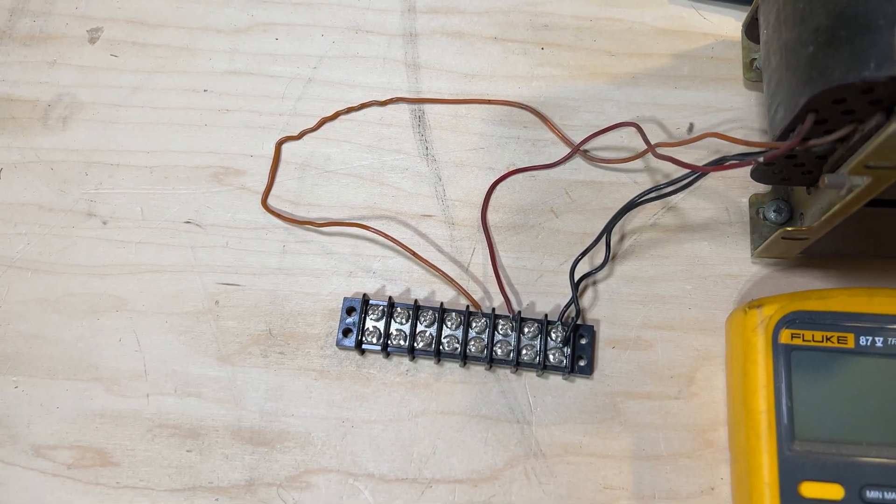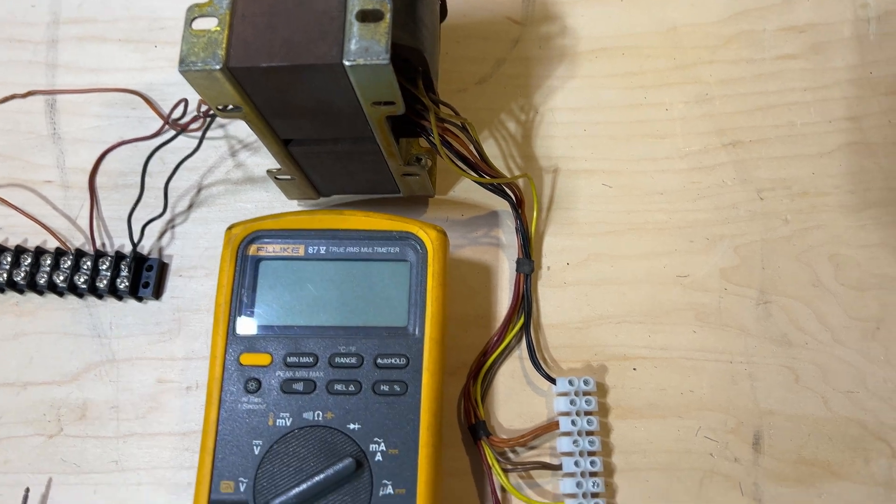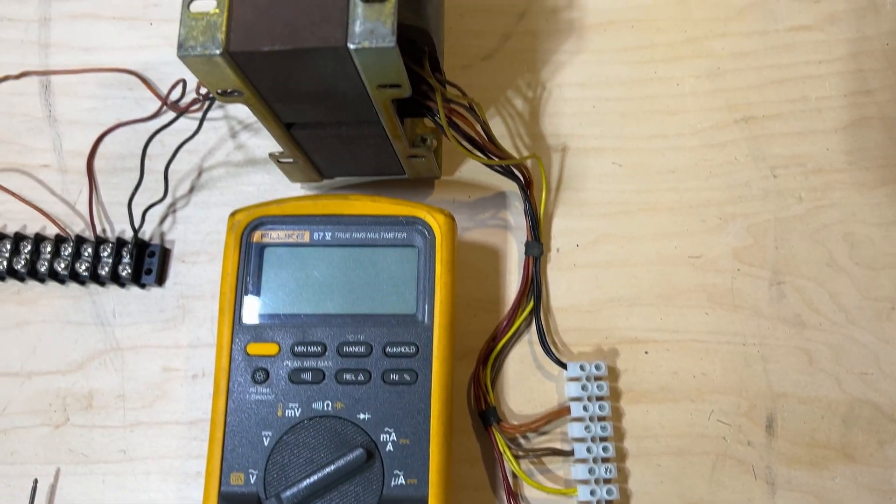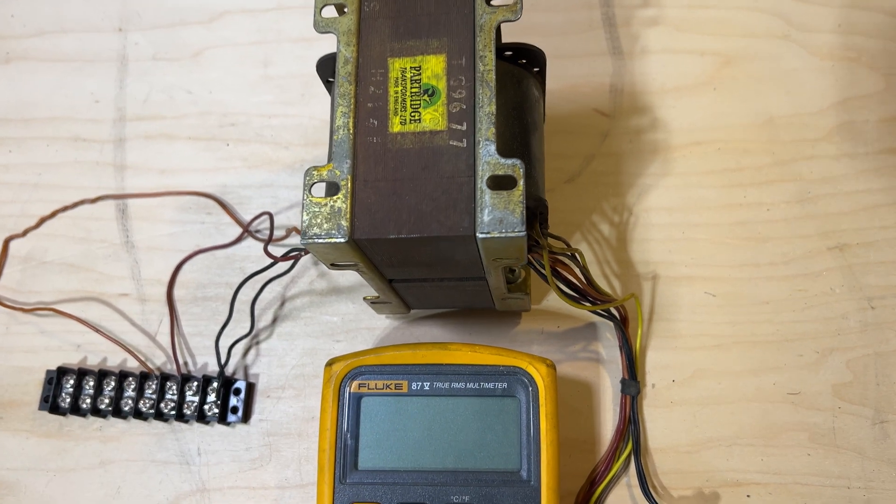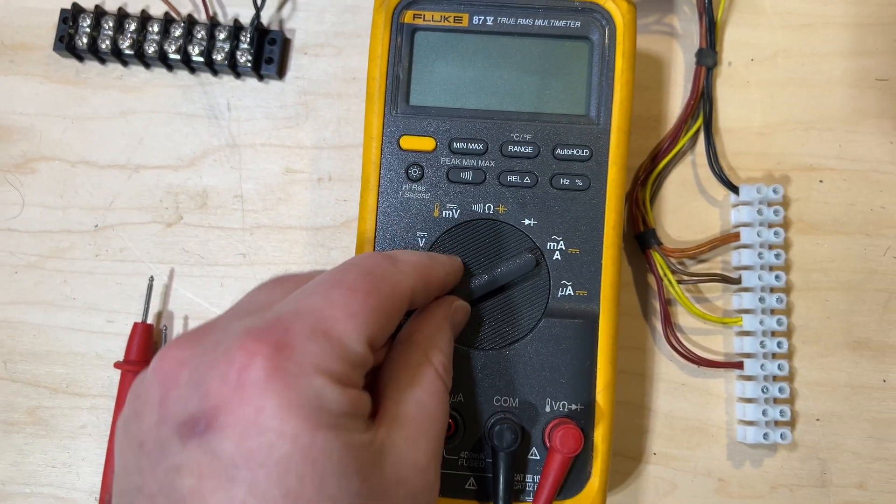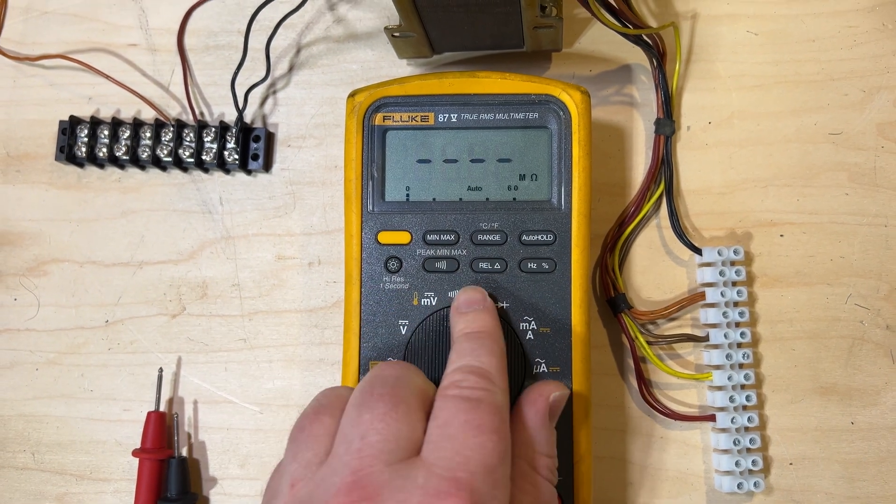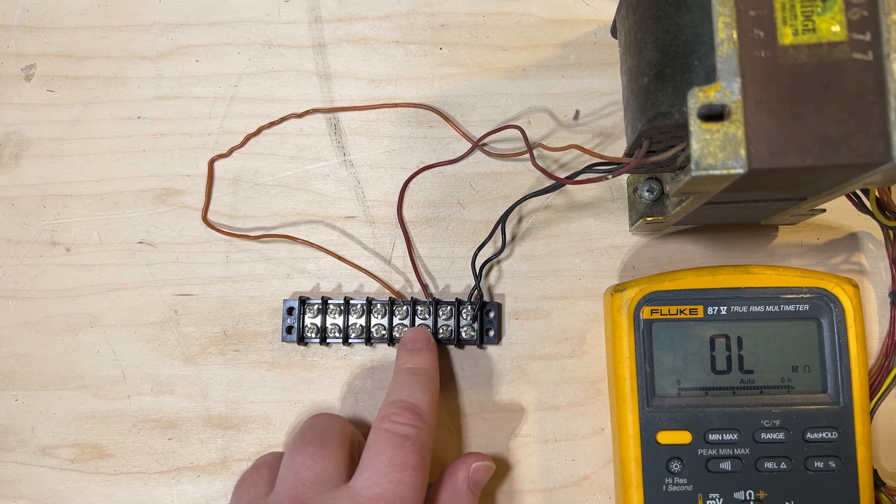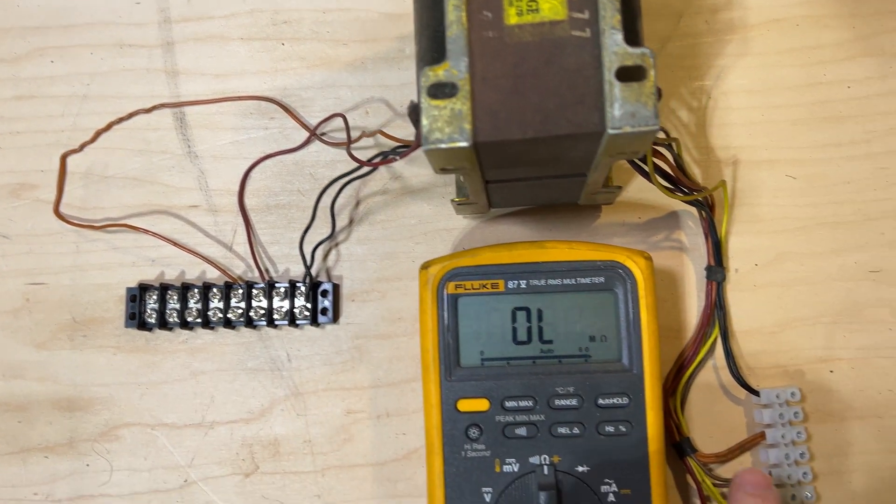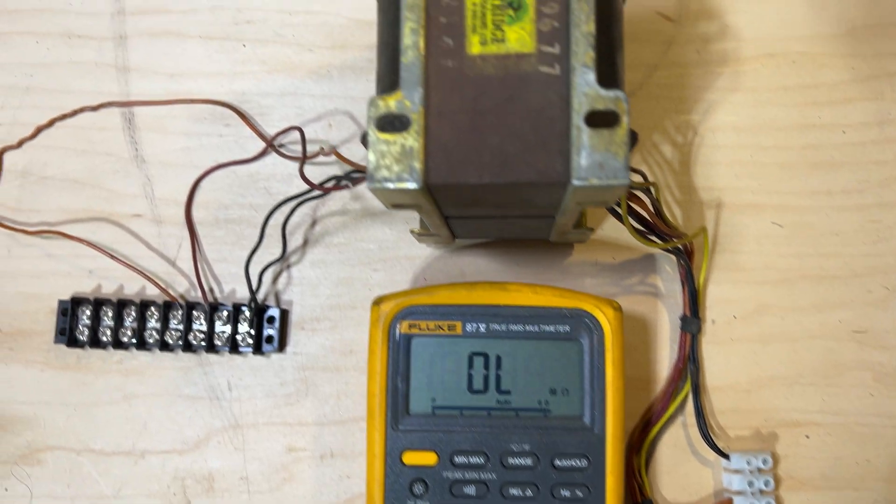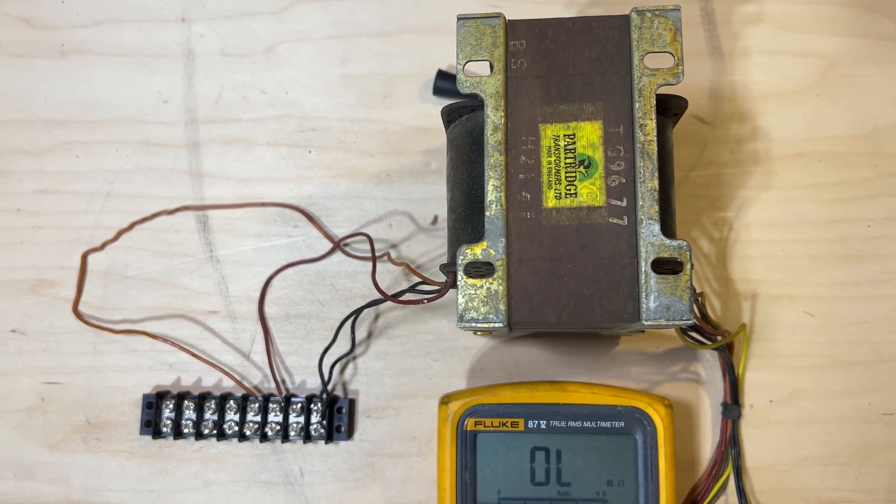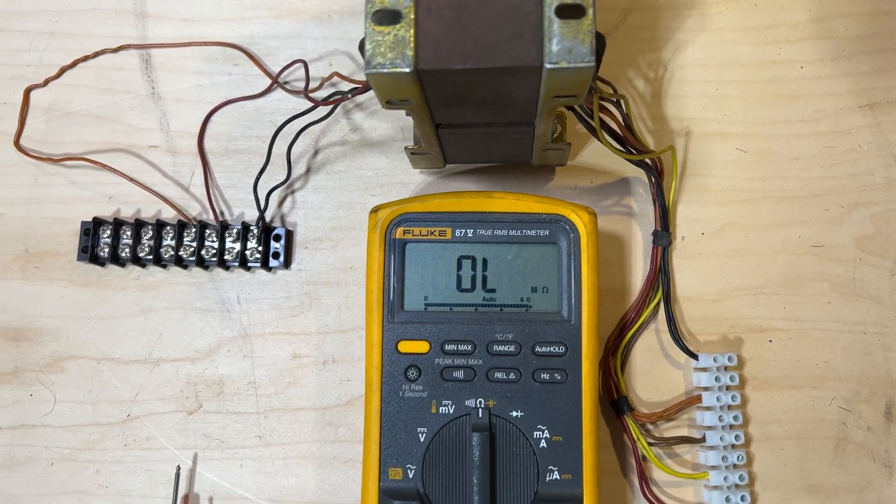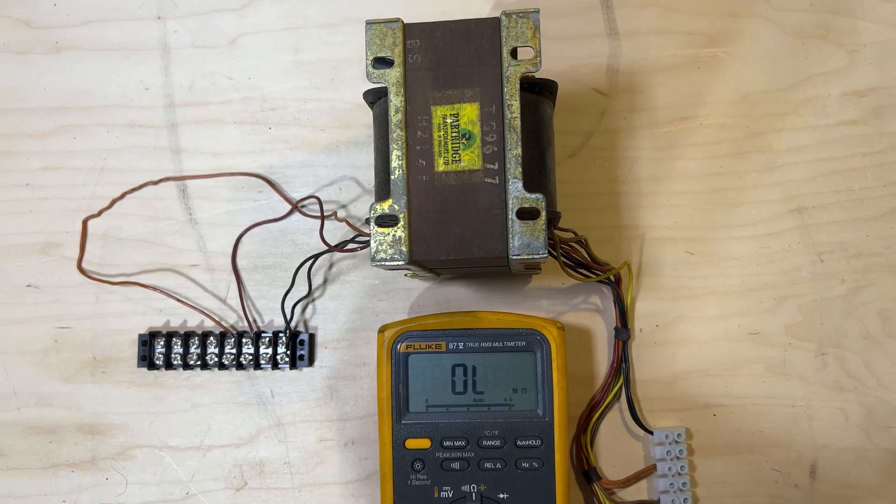So, let's start off with the resistance checks. This is something anybody can do at home. You're not going to hurt anything. The only thing that makes this kind of test dangerous at all is the second test we're going to do where we actually apply voltage. But anybody can take a meter, set it to resistance, and then probe around and measure between wires and see what you can get that makes sense. See if things are connected in a way that makes sense. Make yourself a little diagram to get a good idea of what's going on with your transformer. So, here we go. We'll do that test now. I'll show you what I've found so far.